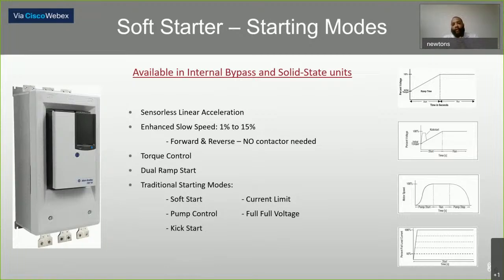Your soft start gives you a controlled start. So you can set a time on how long it will take to get from 0 to full speed. For example, let's say my application was a fan or pump. I don't necessarily need that fan or pump to get to full speed in 1 or 2 seconds. I have more than enough time. I can set it to 10, 15, 20 seconds to have a nice progressive start to get to full speed.